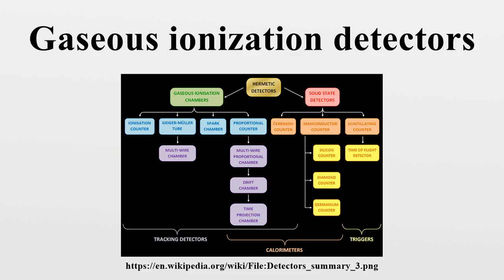Ionization type smoke detectors are gaseous ionization detectors in widespread use. A small source of radioactive americium is placed so that it maintains a current between two plates that effectively form an ionization chamber. However, if smoke gets between the plates where ionization is taking place, the ionized gas can be neutralized leading to a reduced current. The decrease in current triggers a fire alarm.